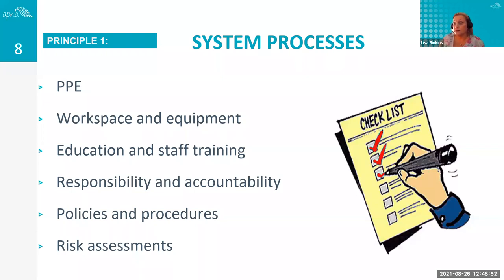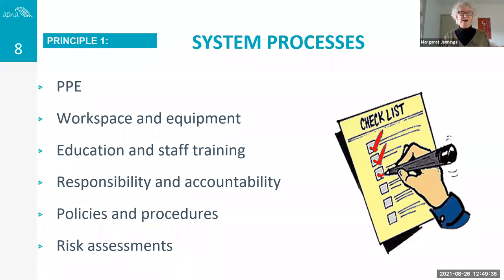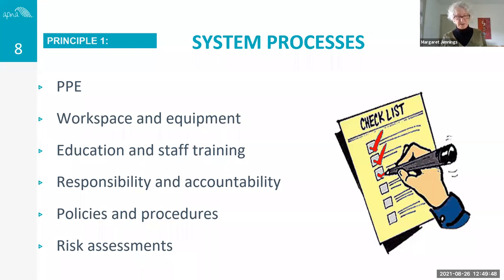Thank you Lisa, and welcome everybody. I'm greeting you from Wurundjeri country. The term I will use for the total process is instrument reprocessing. Number one: please make sure that you're not trying to reprocess anything that's disposable — that is not acceptable, and I do still find people who are unsure. Let's have a look at some of these system processes — this is a cook's tour of the process, and the tips I'm giving are also reminders that may help people who have had questions but haven't yet asked them.